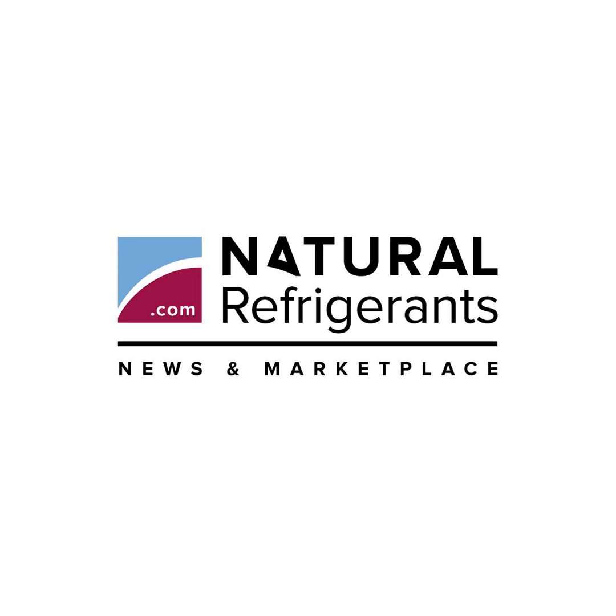The study/scalability. Magnotherm partnered with a supermarket chain that operates tens of thousands of propane display cases to pilot a 0.4 kilowatt, 0.1 tons of refrigeration capacity Eclipse by installing the unit in a retrofitted R290 cabinet. In the 11-week study running from May to September, the retailer confirmed that the Eclipse cabinet used 15% less energy than the incumbent propane cases, while maintaining the target temperature of 4 to 5 degrees Celsius, 39.2 to 41 degrees Fahrenheit. The customer plans to deploy a minimum of 10 more Eclipse units in supermarkets next year, Sirman said.